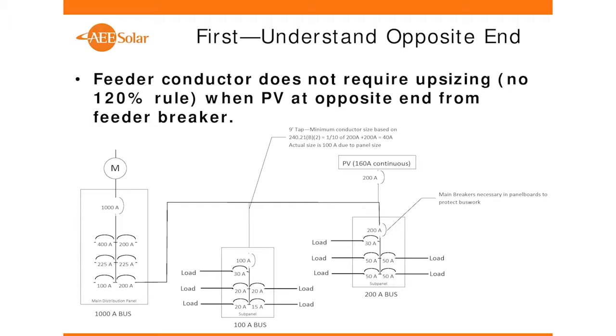Because we've got two sources, right? We've got a 200 amp breaker here and we've got the 200 amp of the PV here. The wire between the two is just fine, but the bus is a problem. So the breaker protects the bus. Whether it had one or not, we're going to have to put one in. Then we're going to talk about taps in a minute, and now we have a tap off of this thing. How do we size that? And we'll talk about that in a second.